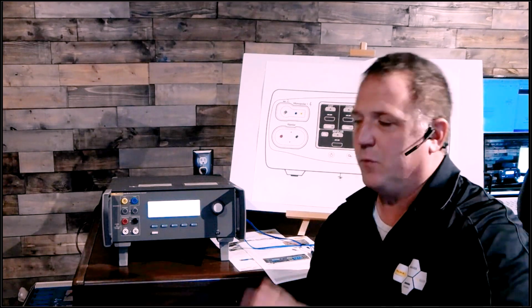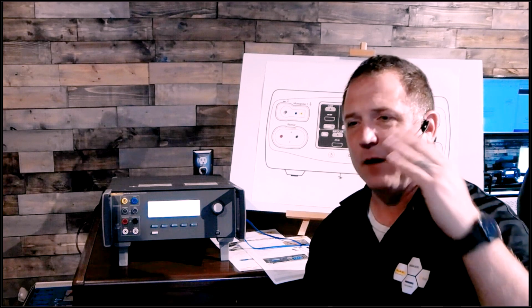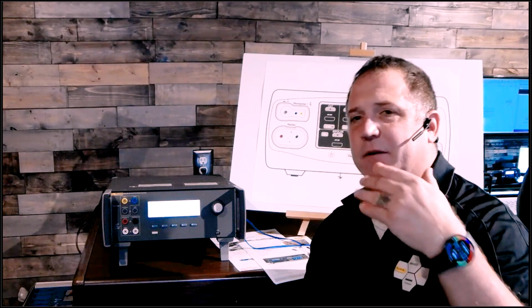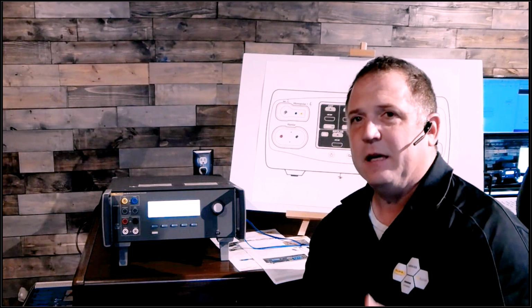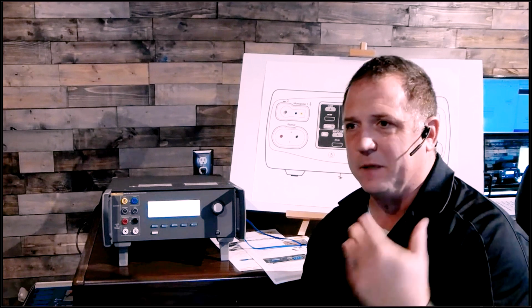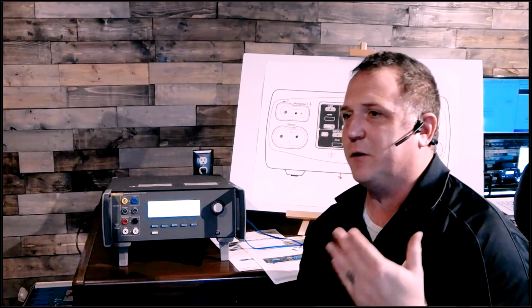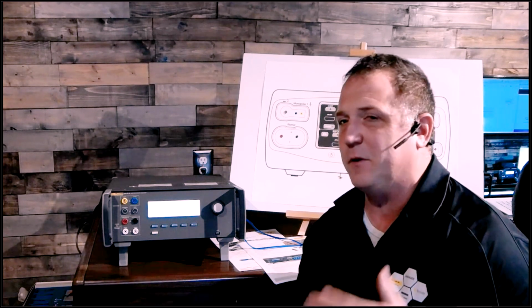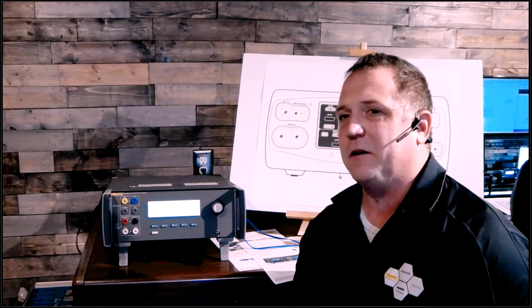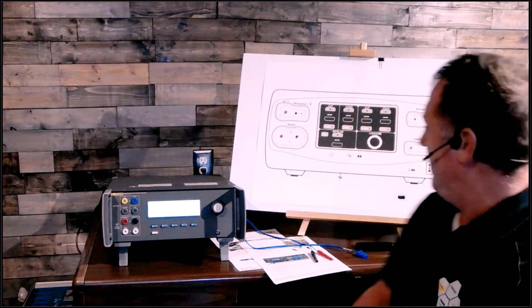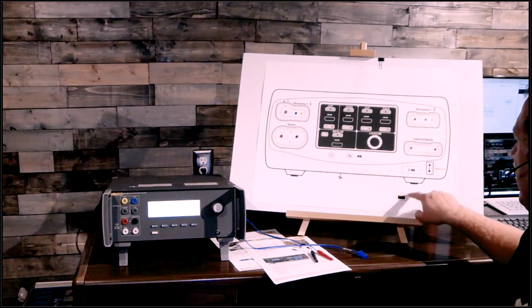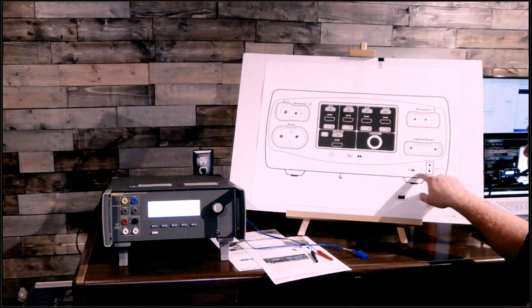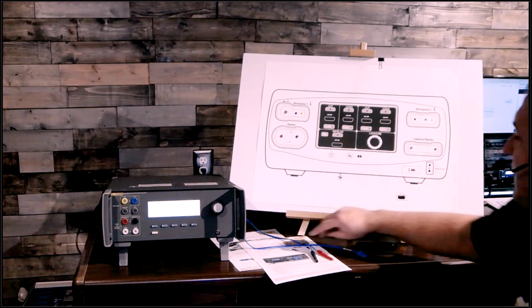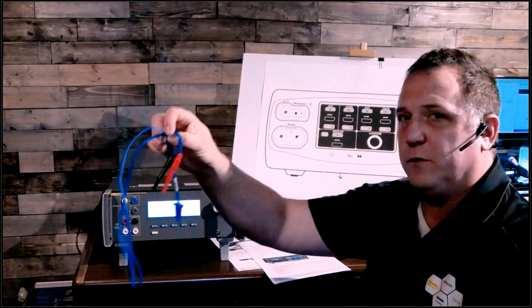Back in the day, a lot of things were single foil pads, and we could test with single foil pads. If you have a modern ESU released within the last few years, you'll notice that if you're not in service mode, it won't allow you to operate in single foil mode. This icon doesn't even exist on many ESUs anymore - the only thing you'll see is the dual foil pad, so you're going to have to use this.